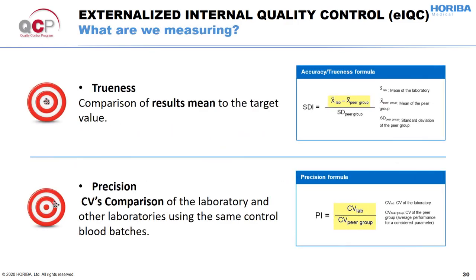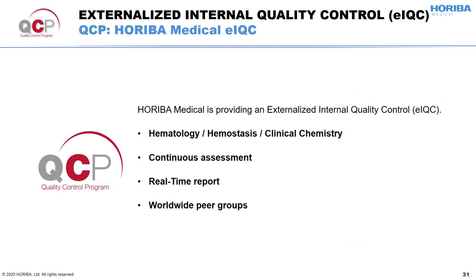What are we measuring? The trueness and the precision. The trueness is calculated by the standard deviation index, or SDI, comparing the monthly mean of the laboratory with the peer group mean. The precision index, or PI, will compare the CV of the laboratory with that of the peer group. Horiba Medical is providing its own externalized IQC, the QCP. It is available for all three disciplines — hematology, hemostasis, and clinical chemistry — and allows access to real-time reports.